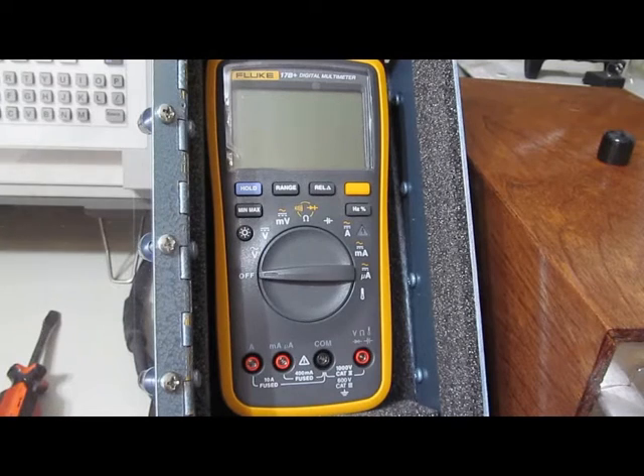So this last set of tests is going to be at 5.9 kV. And I think what we're going to do is measure this again with a scope and just verify this, because it is the high end of the generator. So we'll go ahead and set that up first.